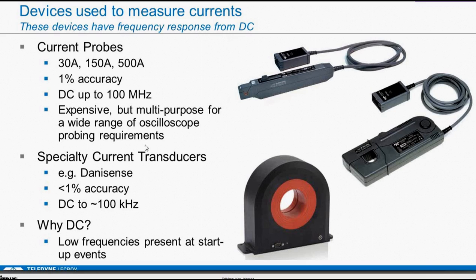For people who don't have that, sometimes they'll use something like a specialty current transducer like this Danisense device here. These are very good accuracy too. The frequency range is a lot less. It's in the low kilohertz range, low 100 kilohertz range. These devices are good for measuring to DC. If you're looking at startup events, especially on a drive output, you really need to be able to reach down to DC to understand what's going on there.